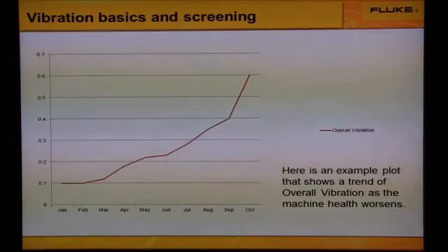Overall vibration analysis does not require extensive training to implement. We get one simple number. Overall vibration meters are valuable as screening tools. If an adverse trend is identified, a more thorough test should be performed to validate the problem and identify the root cause.